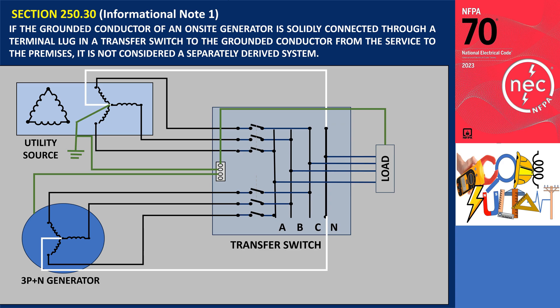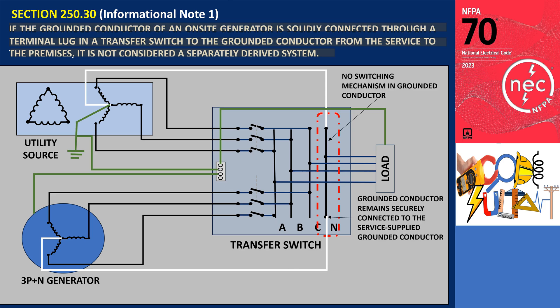According to the first informational note in this section, if the grounded conductor of an on-site generator is solidly connected through a terminal lug in a transfer switch to the grounded conductor from the service to the premises, it is not considered a separately derived system. This occurs when the alternate source transfer equipment does not involve any switching mechanism in the grounded conductor. As a result, the grounded conductor remains securely connected to the service-supplied grounded conductor while the alternate source is functioning and supplying power to the load being served.